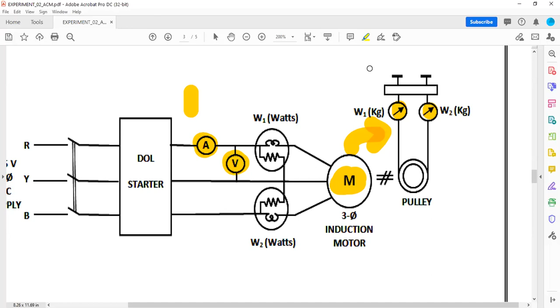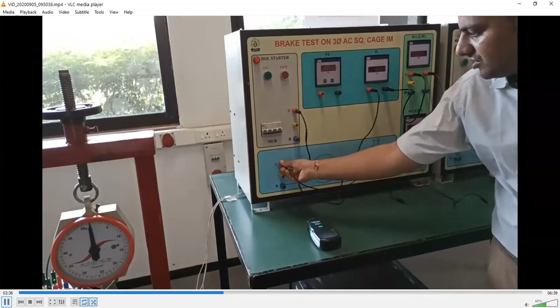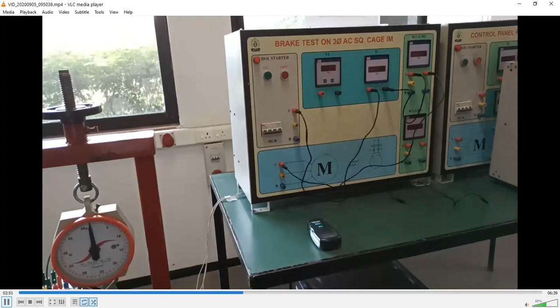So as you can see, this is your three-phase supply which is coming to the panel. So I'm connecting the R phase and I'm taking a current out from the R phase, which is going to the ammeter as you can see on the screen. So current is now going to the ammeter. Now from the ammeter it will go to the R phase of the wattmeter. Now from the R phase of the wattmeter it will go back to the motor. And as you can see, your motor is over here. So from this panel, connections are going to the motor which I already showed you. And I also showed you the motor connection, which is connected in delta. So our motor is connected in delta, so we do not need a neutral over here.